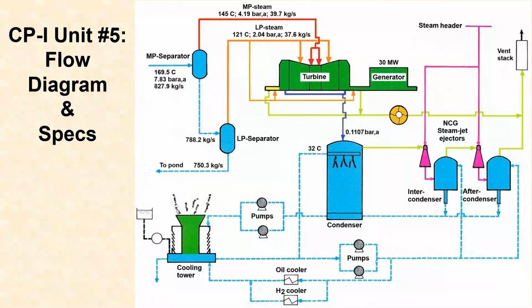Next, the flow diagram, heat balance diagram for unit number 5. I'll just point out a couple of things, fairly standard. Notice that at the end of all the separations, there was 750 kilograms per second of brine that went into the pond. That's a lot of fluid. And notice also that the pressure in this separator is about 2 bar, so it's above atmospheric pressure. So even in those short pipes, by the time it finally got to the end of the pipe, there was yet another flash process which produced some vapor, and all that liquid then went into the pond. The rest of this is fairly conventional, and I don't think we need to go into any of that. Next slide, please.